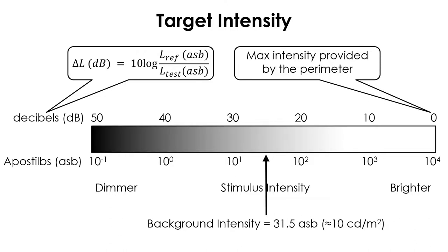Test locations where the patient is unable to see a stimulus of the highest possible light intensity that can be generated by a perimeter are assumed to be totally blind at those locations, even though they may still be able to see brighter lights if available. For those locations, a value of zero decibels is assigned. Therefore, when the range of stimulus intensity provided by a Humphrey machine is 0.1 to 10,000 ASB, that range corresponds to 50 to zero decibels, respectively.